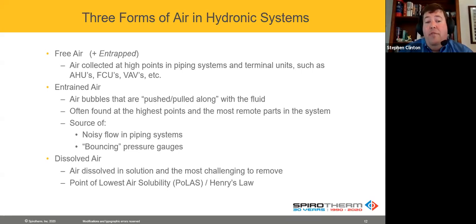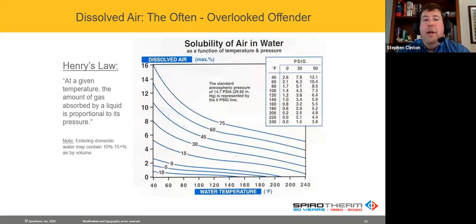The other part is dissolved air, and dissolved air, oftentimes we don't think about that. At a presentation a year or so ago, a little term came to me: the often overlooked offender. And we need to think about that because this is very important. Let's look at it this way. Let's say that every gallon of water that you bring into a system, you fill that system up with 60-degree water at 60 PSI. That water, per Henry's law, which says the amount of air that water can hold in solution is directly related to the temperature and pressure, can hold up to 10.4% by volume of dissolved air.